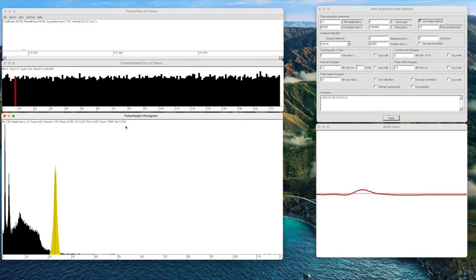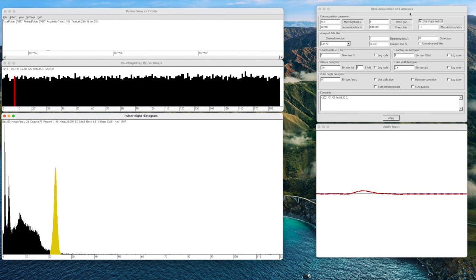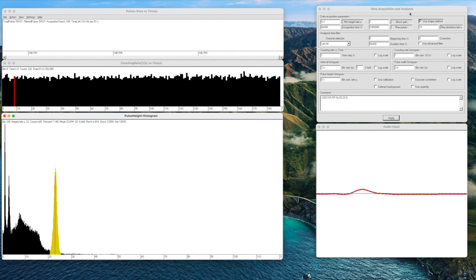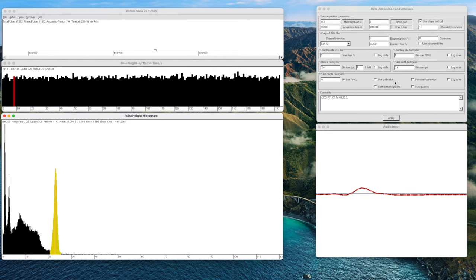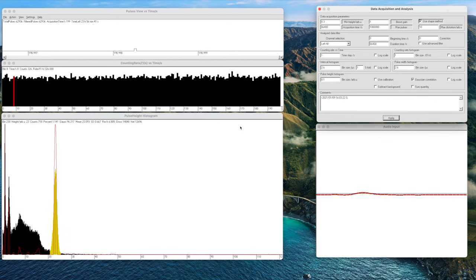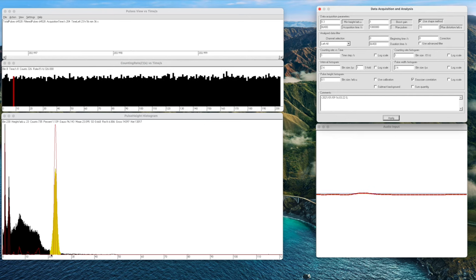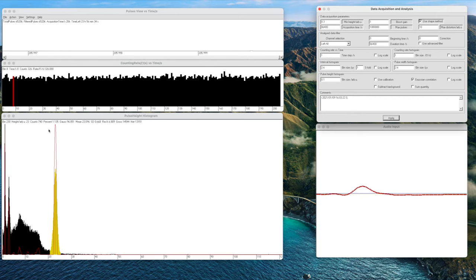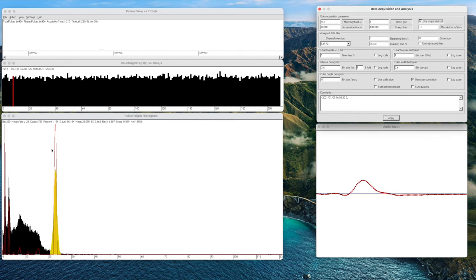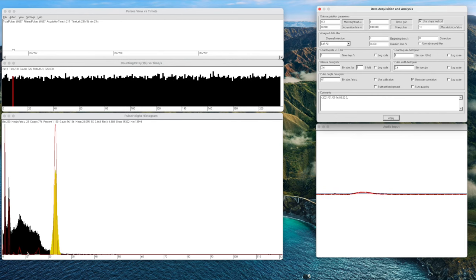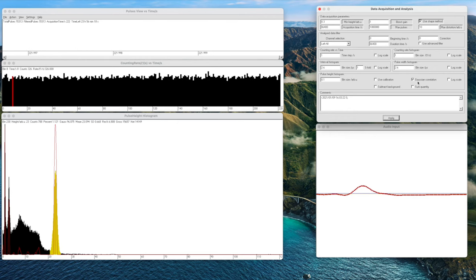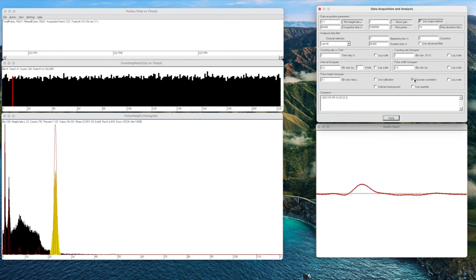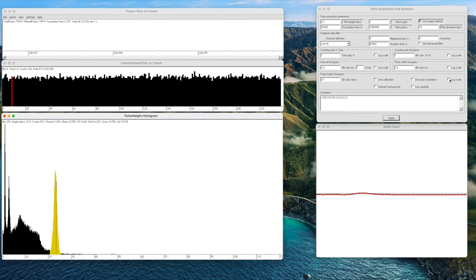This could be very important. While this is running we can also go and look at some of the other features that we have here to help us analyze our spectrum. There is a very neat feature here called Gaussian correlation. If we turn that on it has a red line overlay on our spectrum which is the Gaussian average of the bins and you can see it enhances the peaks. So it sometimes can bring out peaks which you otherwise aren't able to see and they show up very clearly with the Gaussian correlation switched on.